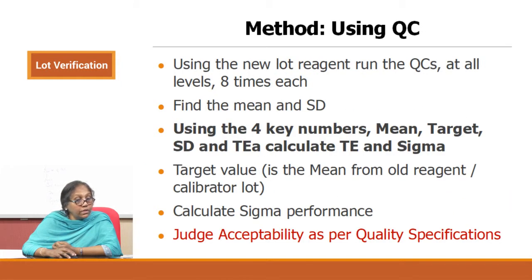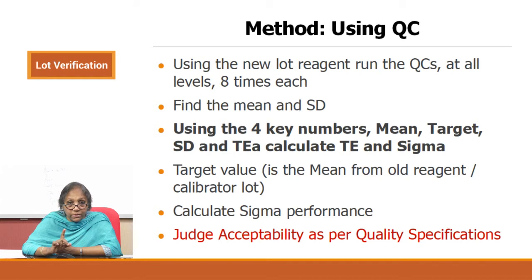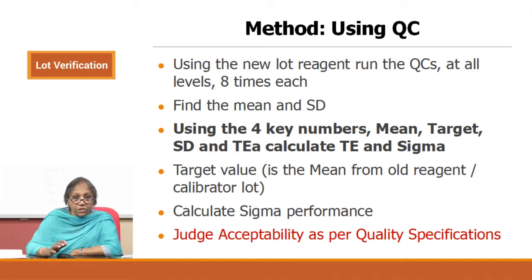Using the new lot reagent, run the QC at all levels. If you have three levels of QC, run all three, with at least 8 runs required. Find the mean and SD, and using the sigma and total error calculations, find your sigma metrics. The target value is the mean from the old lot — that is the key thing to remember — because you are trying to find the difference between the new and old lot. Then calculate the sigma performance and judge acceptability as per your protocol.